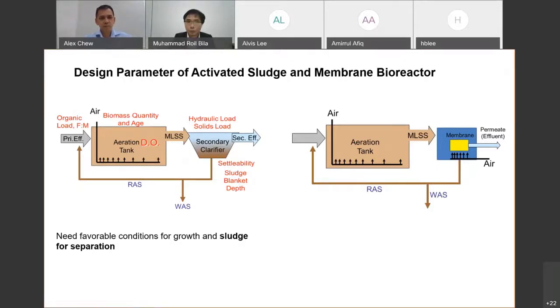And eventually we will have acceptable effluent quality. So when we do MBR, as you can see here from left to right, the difference is only on the second one. Here, instead of having a clarifier, we have a membrane system, and for the membrane system we install extra aeration here. The aeration here is for membrane cleaning.